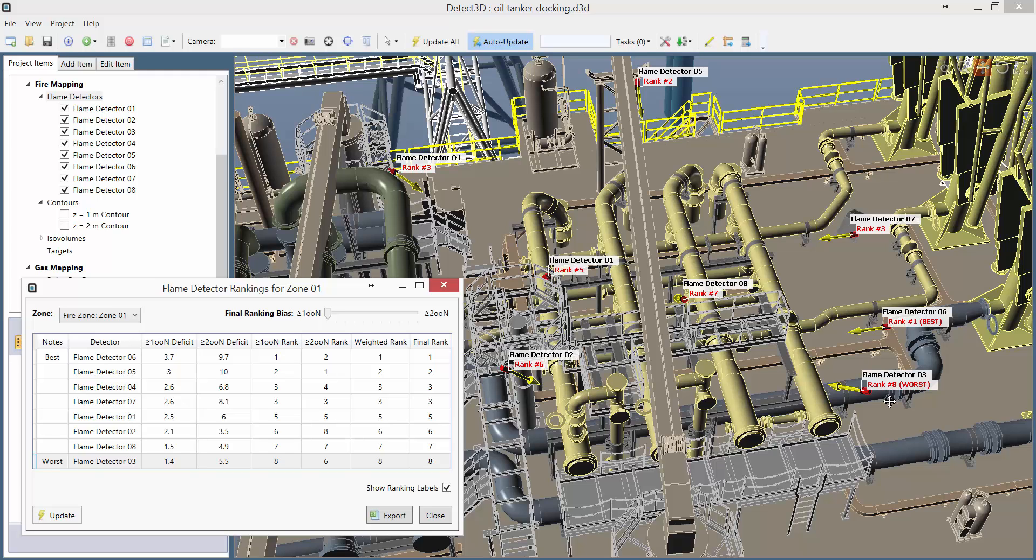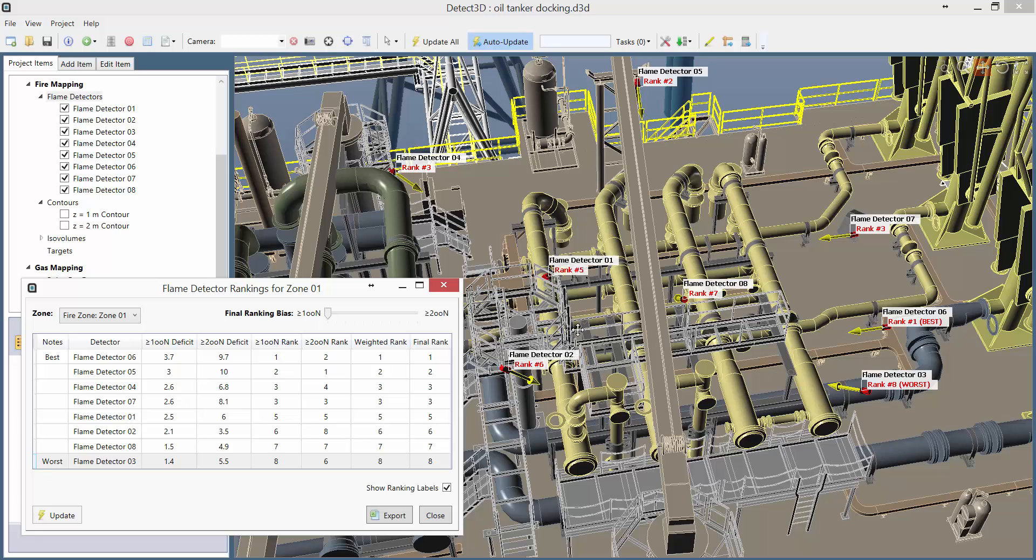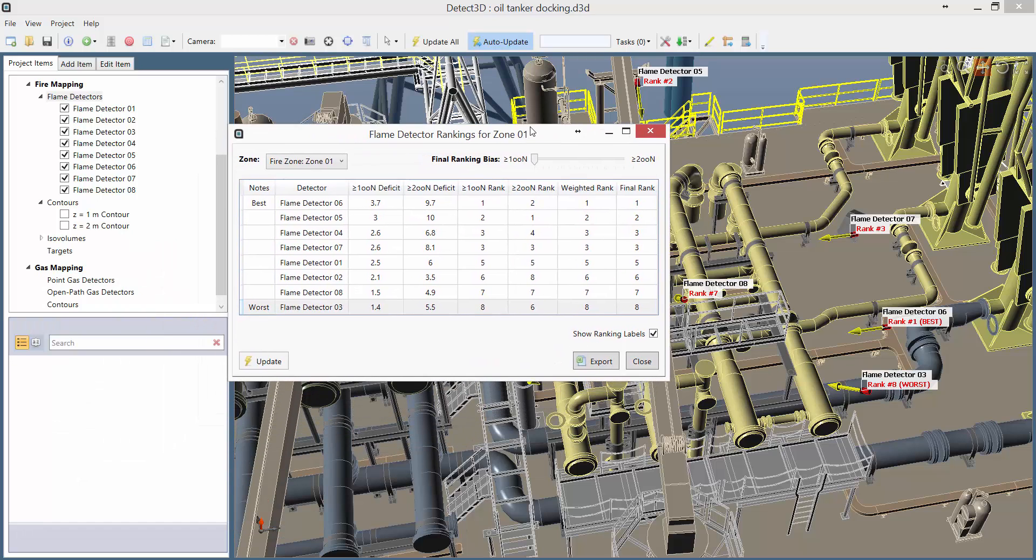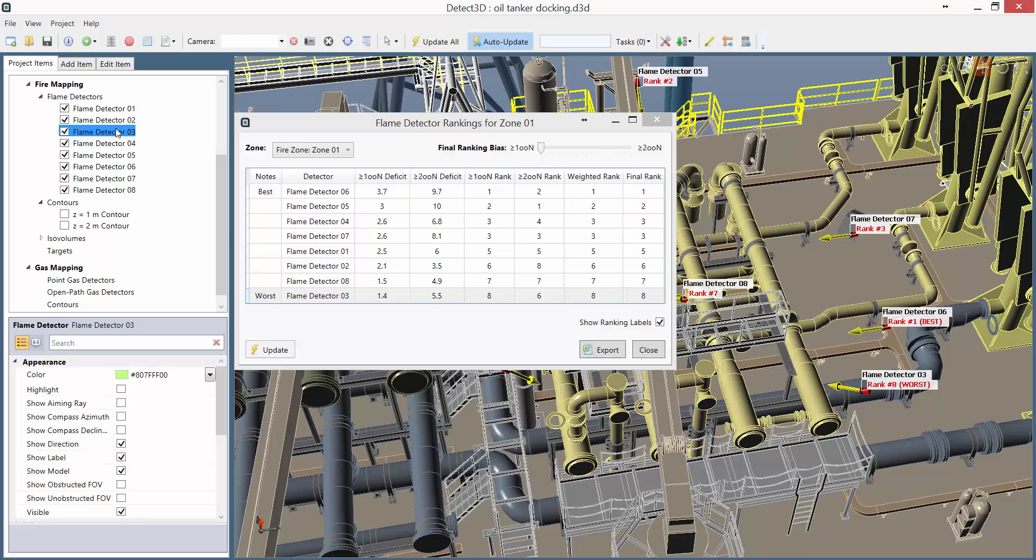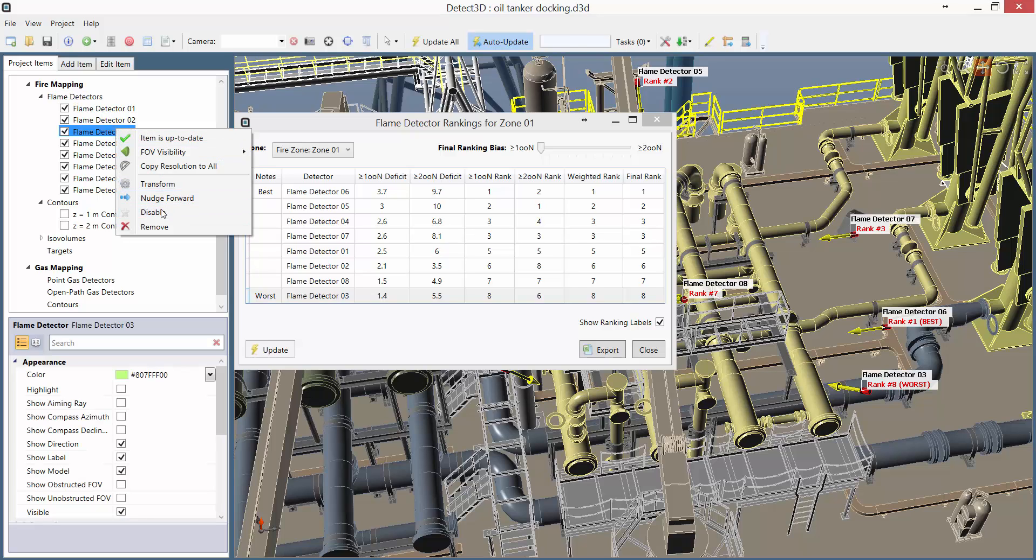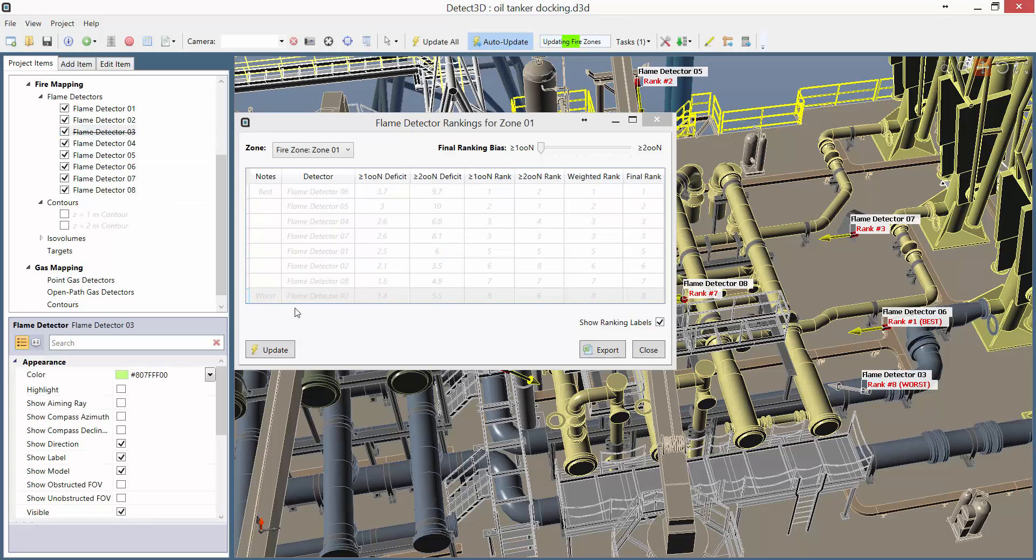In this case, Detector 3 is so ineffective that it will only dock 1.4 percentage points from the 1 out of n coverage, reducing it from 92.2% to 90.8%, still above the 90% target. In other words, the ranking tool is telling us that we can remove Detector 3 entirely. Instead of deleting it, I'm actually just going to disable it, which effectively switches it off.